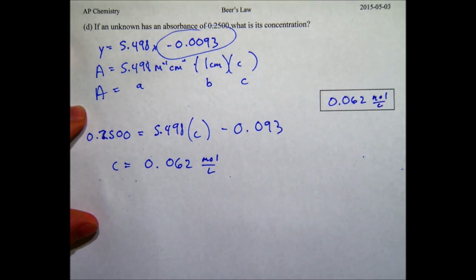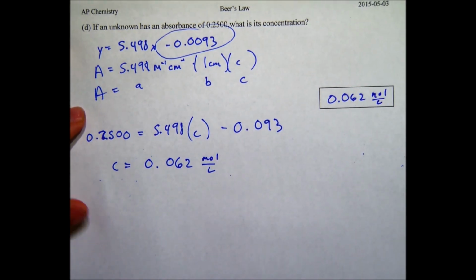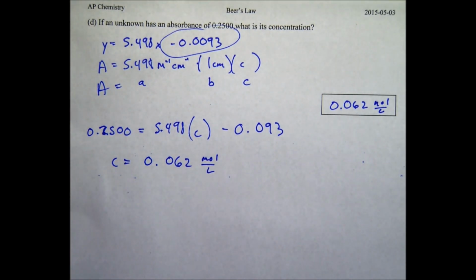So that's all we have to do now. Once you have the standard curve, imagine standardizing this for a particular analyte. Once it's standardized and it's not touched and it's running, of course you should calibrate every so often. You can continually run unknowns through relatively quickly, get the absorbance from the instrument, plug it into your calibration curve, and you'll know exactly what the concentration is.